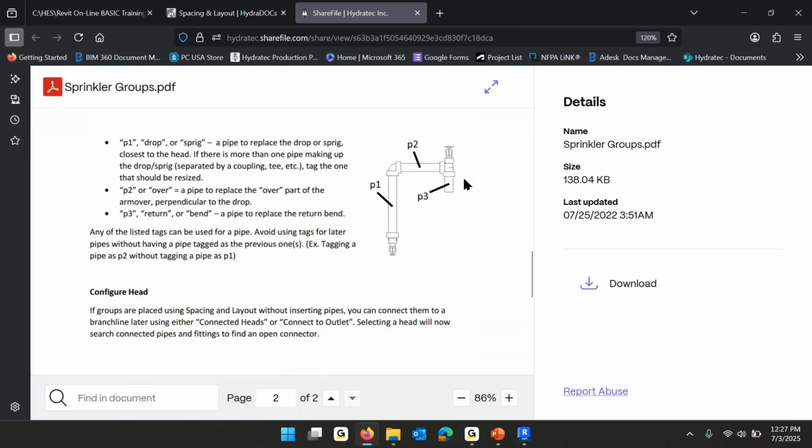you want. So here was another example. I want to be able to go up, over, and down. I think on the West Coast, I've heard this called a rooster tail. We're putting this there for the above combustible concealed space, and then we're going over and down to get below the combustible concealed space. So you could draw this out, call it a group, and then use this as the sprinkler head instead of the sprinkler head itself, and it'll draw that whole extra thing.